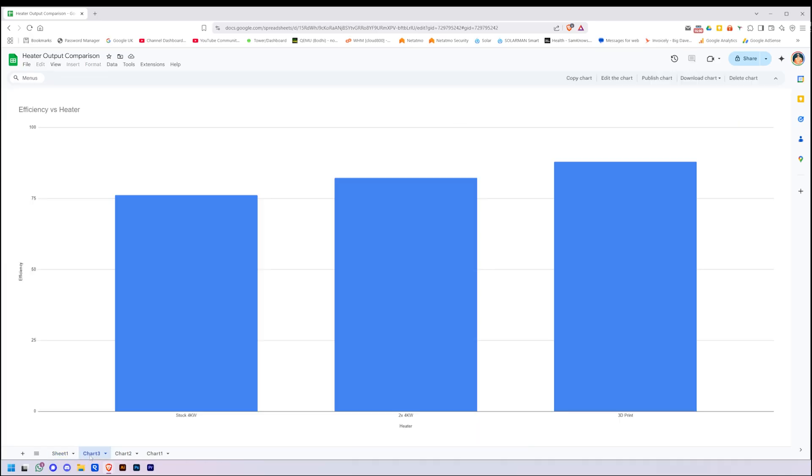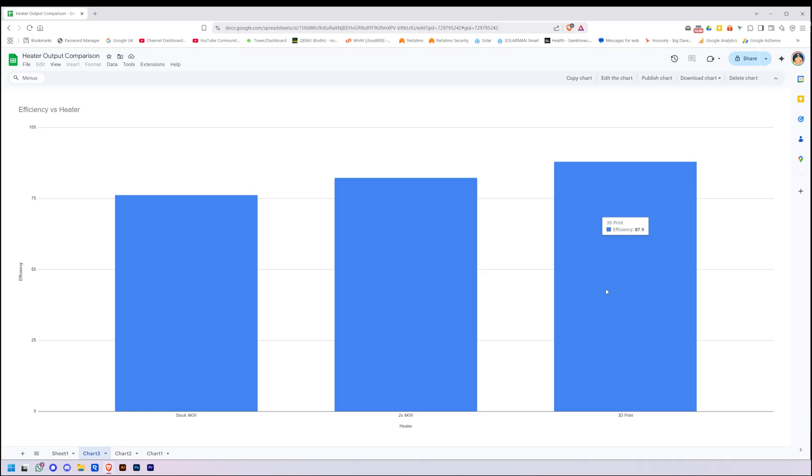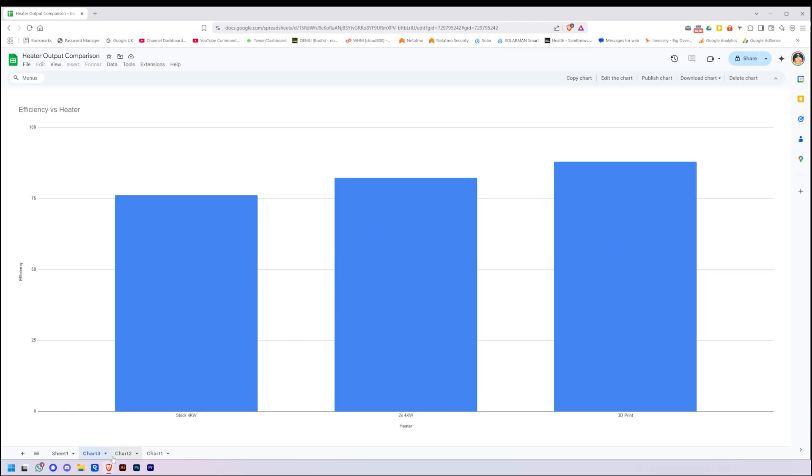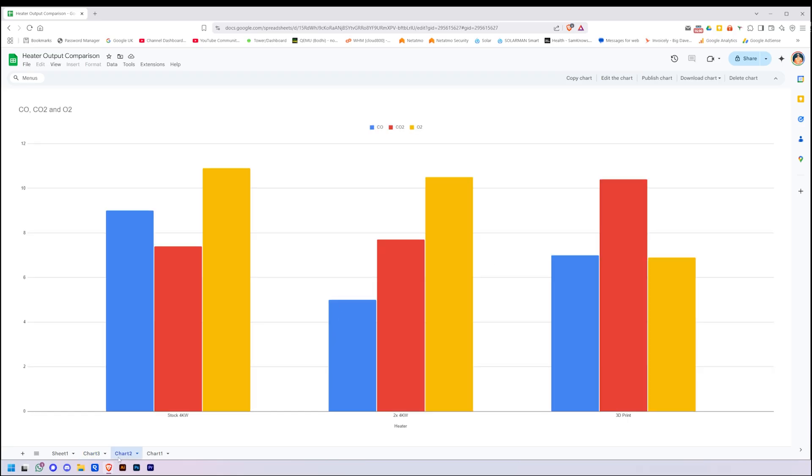Let's have some charts. Charts are much easier to look at. So this is the efficiency as calculated by the TPI gas analyzer. Stock 76, two fours stuck together 82, and then the big 3D printed one a nice 88. So an increase in efficiency with size. Perfect, that's what we want to see.